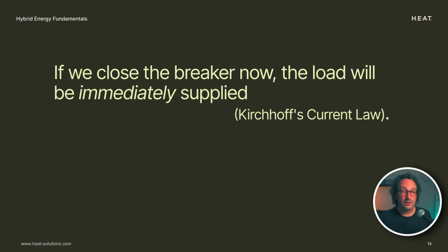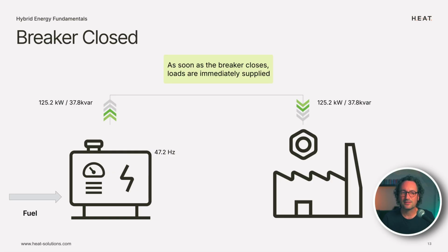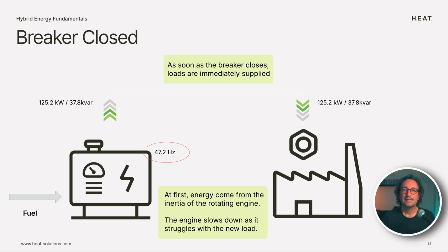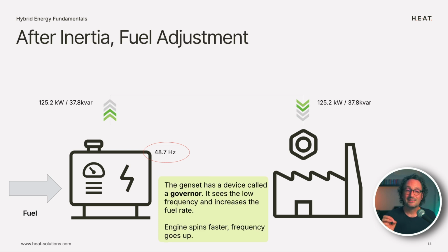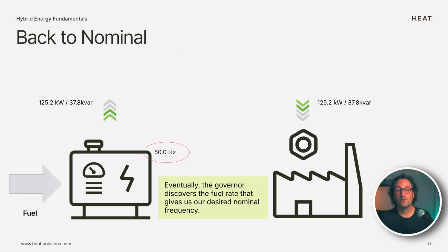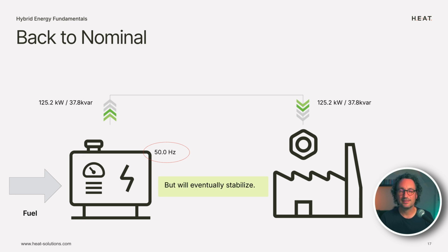We just learned that if we close the breaker, Kirchhoff's current law guarantees that the load will be immediately supplied. We're probably going to need more fuel. So let's see what happens. We close the breaker, the loads are immediately supplied, and at first, the energy for that load comes not from the fuel, but rather from the inertia of the spinning genset. And as we take that energy out of the spinning genset, it slows down as it loses some of that inertia. The genset has a device called a governor. This can see that the frequency is reduced, and it responds by increasing the fuel rate to try to speed up the generator and get us back to 50 hertz output. Eventually, we're going to hit that nominal frequency of 50 hertz. We might even overshoot a little bit, but eventually we'll stabilize, and the governor will make sure that it's found the correct fuel rate for the current load that the factory has.